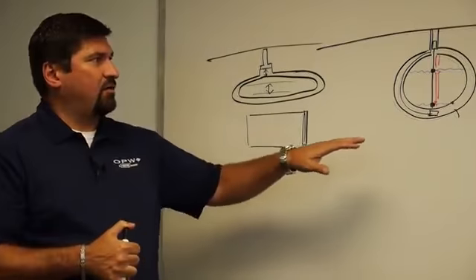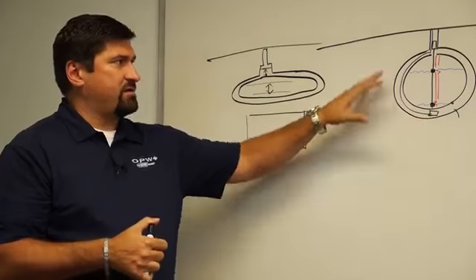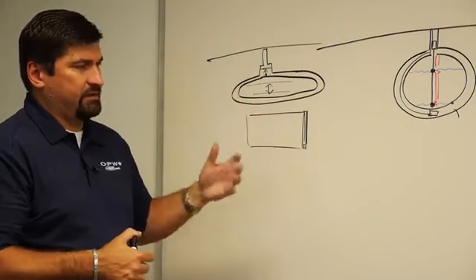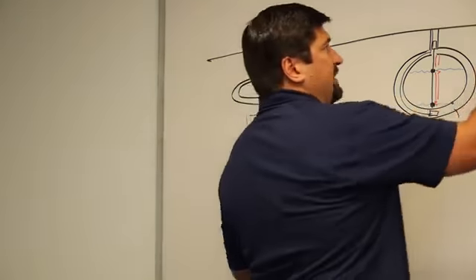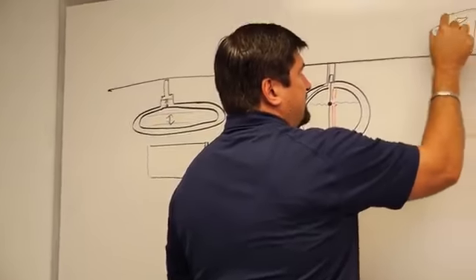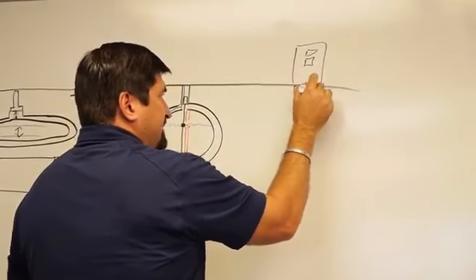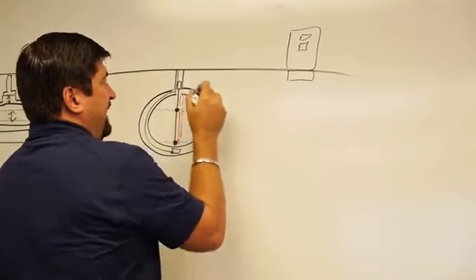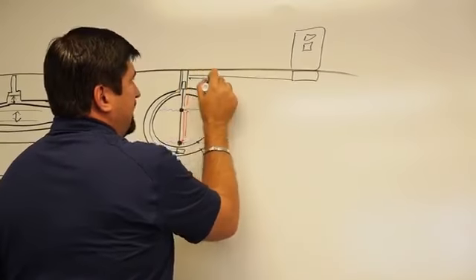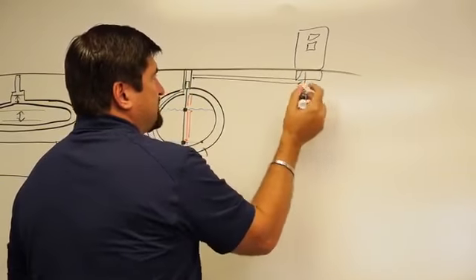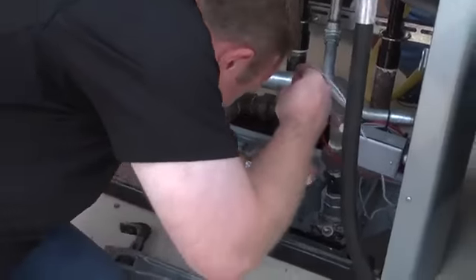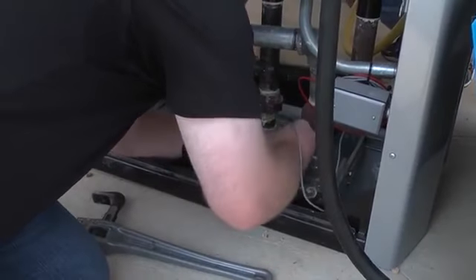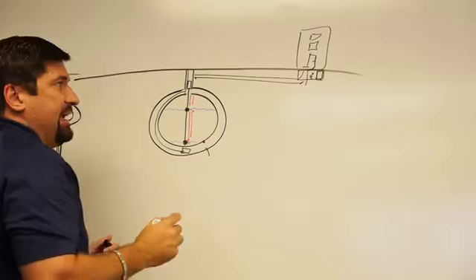So tank gauges not only monitor the level of the tank or the surrounding areas of the tank in the annular space. When you take that same example that we had before with the little dispenser, underneath this dispenser there is something, either a dispenser pan or a dispenser sump, where that piping from the tank comes up underneath the dispenser. You can actually put in a sensor here to let you know if this piping or any of the piping underneath the dispenser is leaking and collecting in this pan.